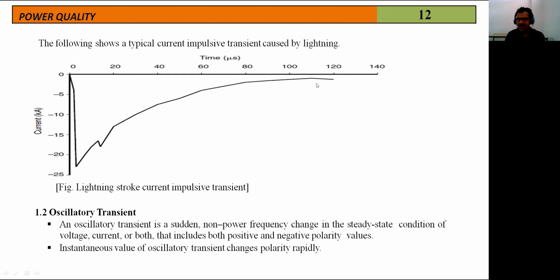It will completely vanish and normal current will flow through the circuit. Coming to the second one, oscillatory transients. An oscillatory transient is a sudden, non-power frequency change in the steady state condition of voltage, current, or both, that includes both positive and negative polarity values. It is also a sudden change in the steady state condition of either voltage or current or both, but it includes both positive as well as negative polarities.